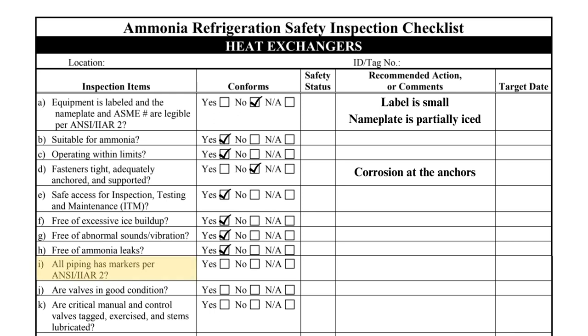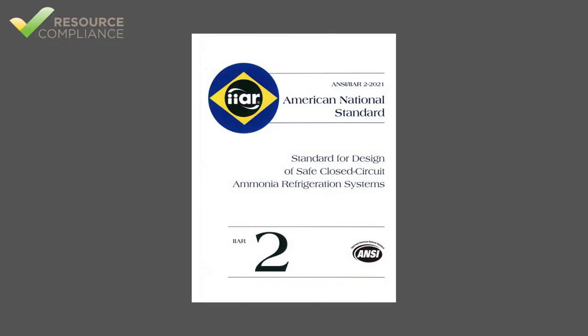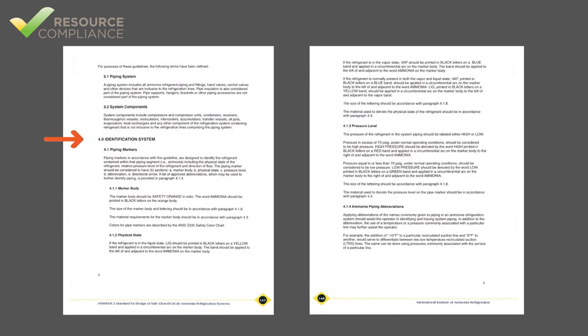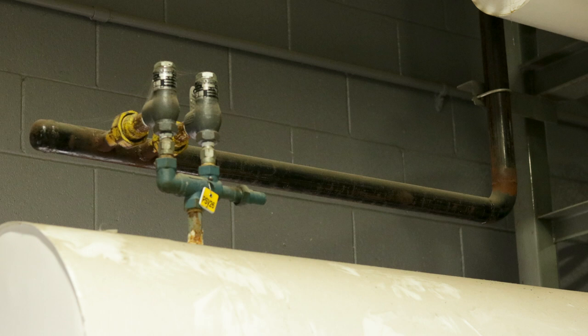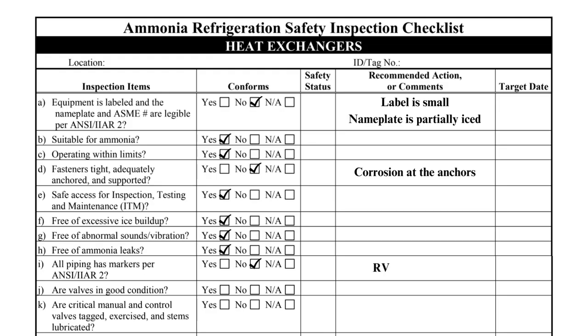Item I inquires if the pipes are marked as required by IIAR Standard 2. Standard 2 requires piping mains, headers, and branches to be labeled with the following: the word ammonia printed in black letters; the physical state abbreviation, LIQ or VAP; the relative pressure, high or low; an arrow depicting the direction of flow in the pipe; and a service abbreviation indicating the purpose of the pipe. Since the relief valve discharge pipe is not labeled, it does not conform and must be listed as a deficiency.